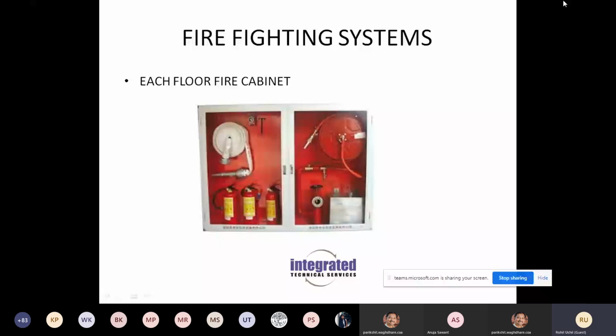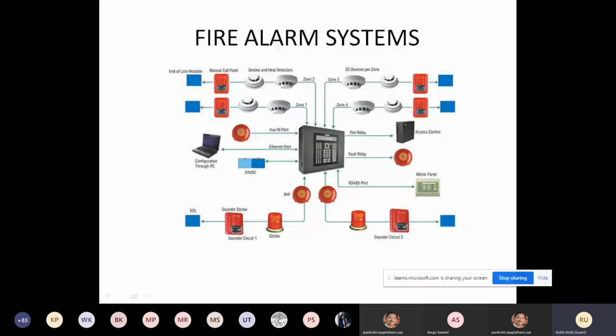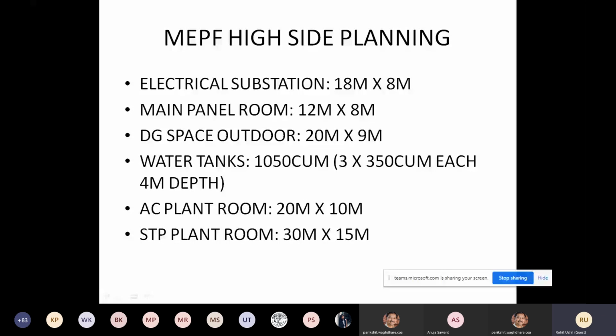This is some idea, for students who are planning a building, just to understand the kind of spaces that we have to provide for in the basement for these various utilities. Like an electrical substation for a building of maybe about 300 to 400,000 square feet. That's what most of the size of the built spaces are in a tall building, approximately 18 meters by 8 meters. It varies depending upon the capacity. Then you need to provide about 12 meters by 8 meters for the main panel room.